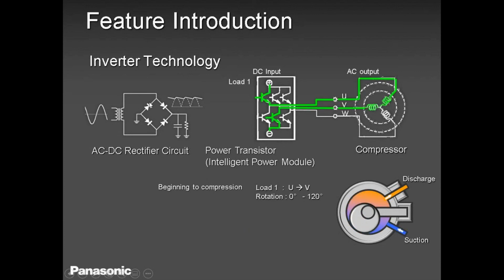it will send the information to that microprocessor. That microprocessor will send the signal to the compressor: Hey, buddy, please ramp up, man. We need more cooling, or we need more heating. So these sensors are very critical, very important to be in a good operating state, so that they send a signal to the board, to the microprocessor, and the microprocessor sends the signal to the compressor.